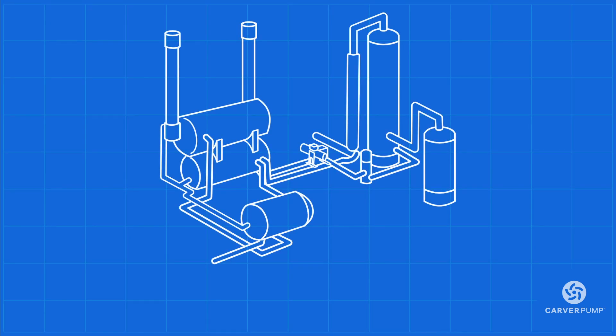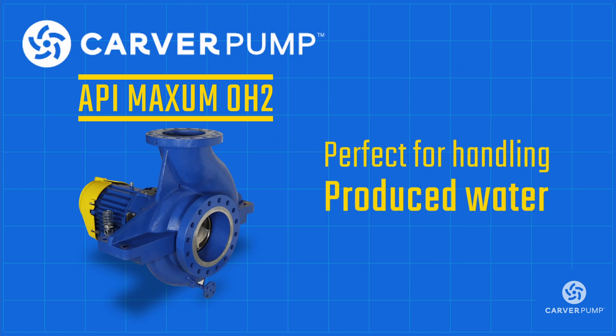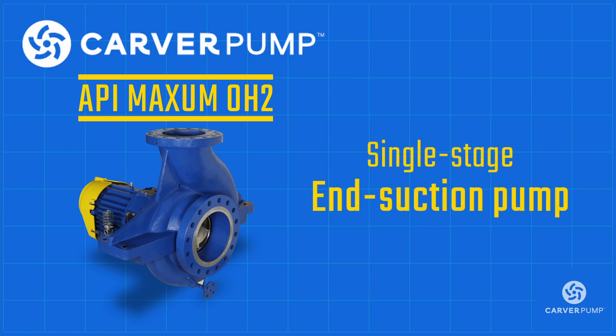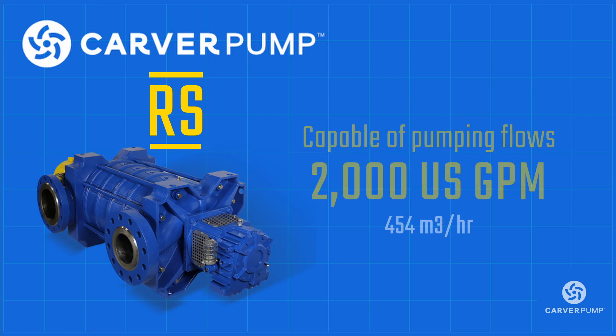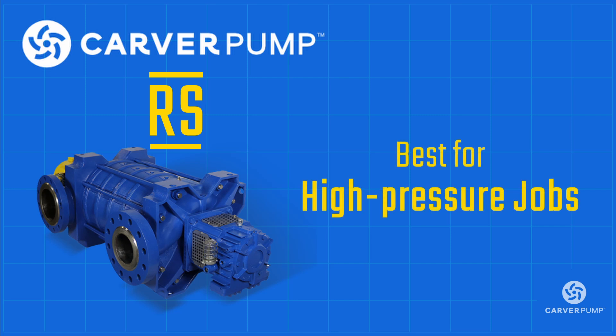As you just saw, there is a bunch of different equipment used in the treatment of produced water. However, perhaps one of the most vital of them all is the produced water pump. Produced water pumps play the critical role of transferring the water from station to station. A pump like the API Maxum OH2 by Carver Pump is perfect for handling produced water, with flows up to 11,500 GPM and heads up to 720 feet. This single-stage end-suction pump is more than capable of taking produced water from one treatment station to the next. However, for high-pressure applications, you may need a multi-stage ring section pump. Carver Pump's RS was built for this task, with flows up to 2,000 GPM, heads up to 3,400 feet, and pumping pressures up to 1,500 PSIG. The RS is your best bet when it comes to high-pressure jobs.